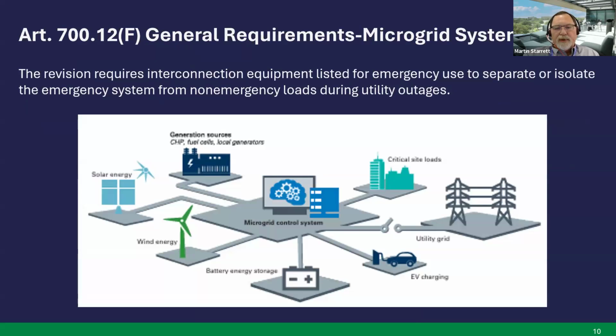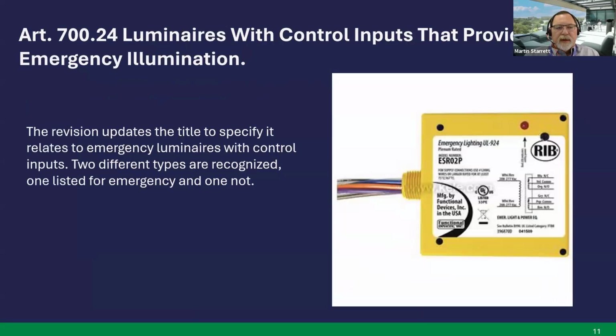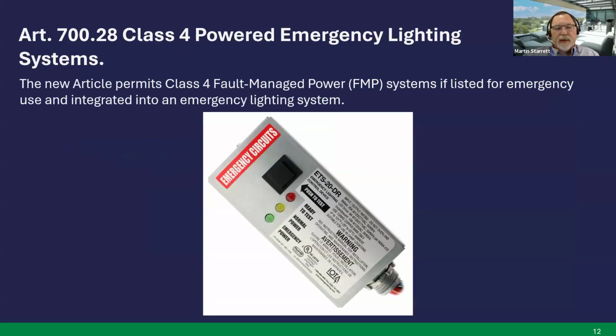Article 712F, general requirements, microgrid system. The revision requires interconnection equipment listed for emergency use to separate or isolate the emergency system from non-emergency loads during utility outages. Next slide. Article 724, luminaires with control inputs that provide emergency illumination. This revision updates the title to specify it relates to emergency luminaires with control inputs. There are two different types recognized, one listed for emergency and one not. Next slide. In Article 728, Class 4 powered emergency lighting systems, this new article will permit Class 4 fault managed power systems if listed for emergency use and integrated into an emergency lighting system. Next slide.